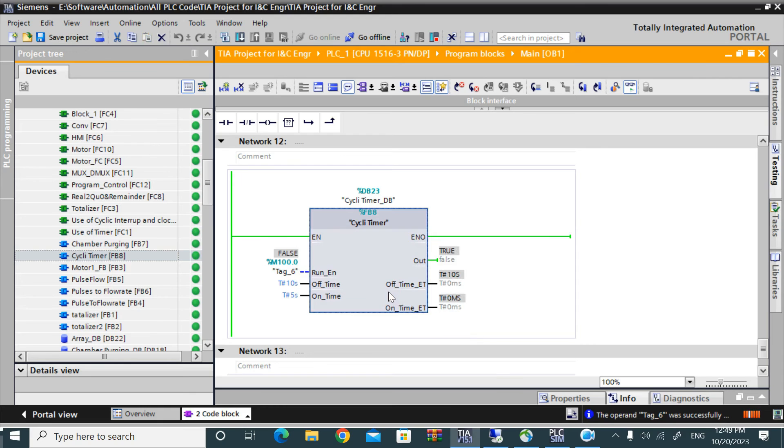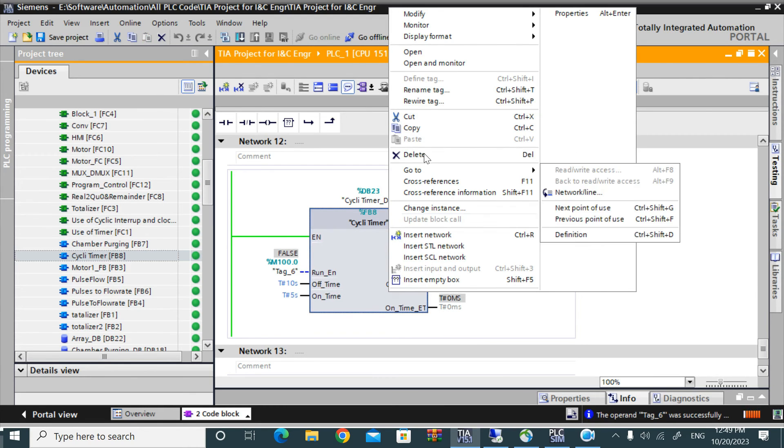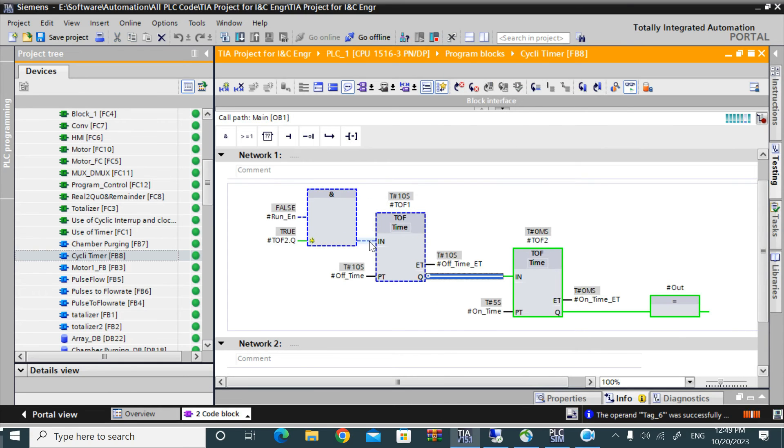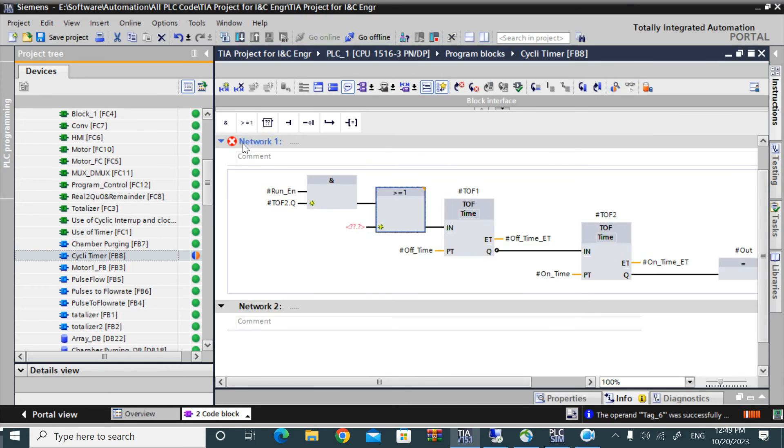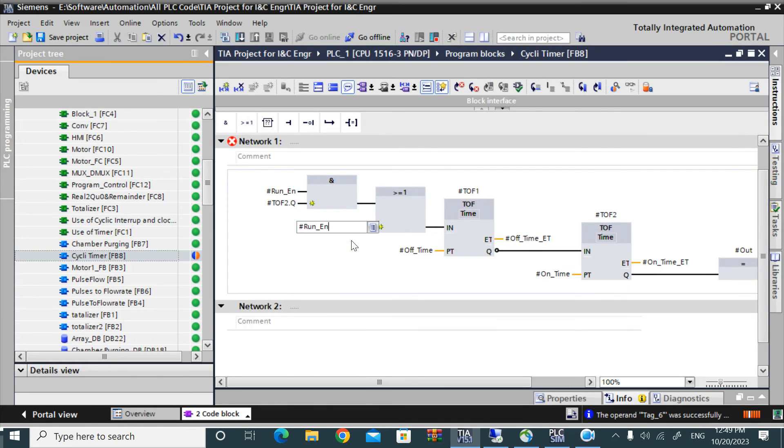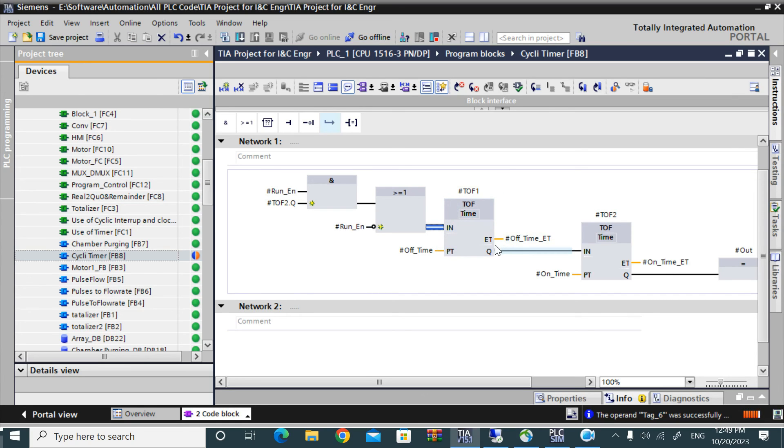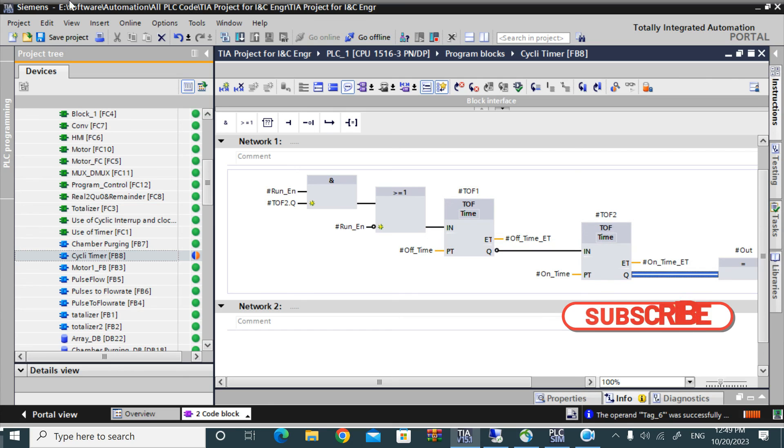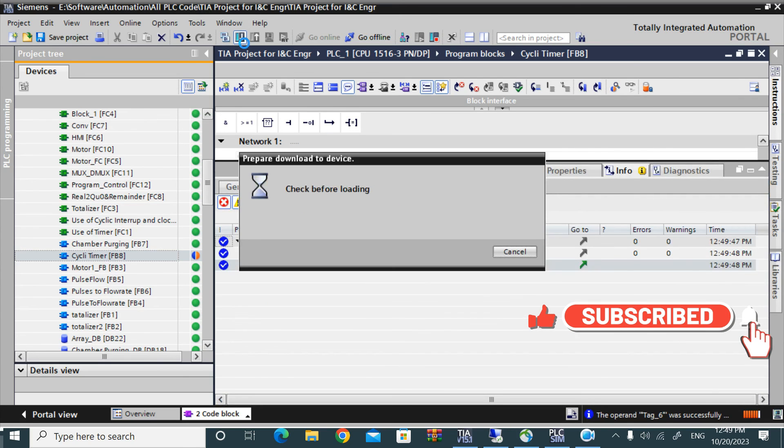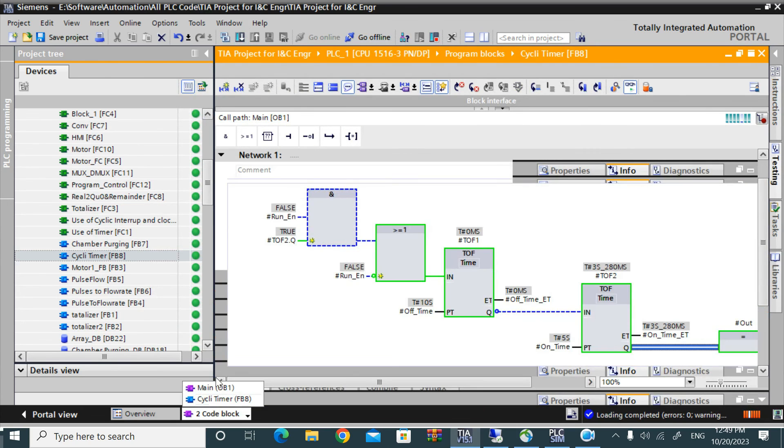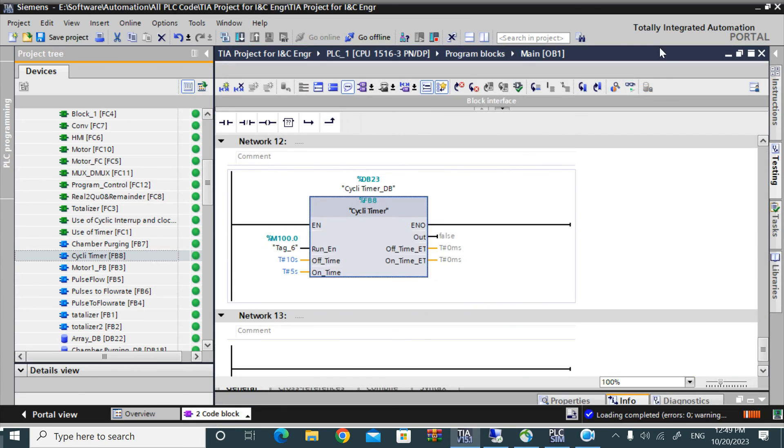So for that we will use an OR gate here. And here I will use run enable pin and give an invert. Means when run enable is off, plus one to TOF. So if there is an input high, the output is high. After that invert pin, it is zero, so there is no input to TOF. Download that to main OB and check.